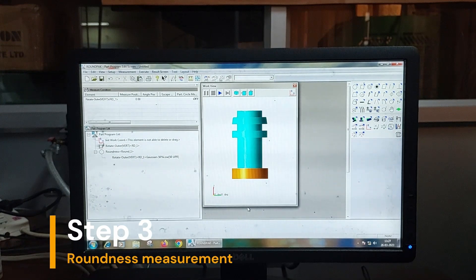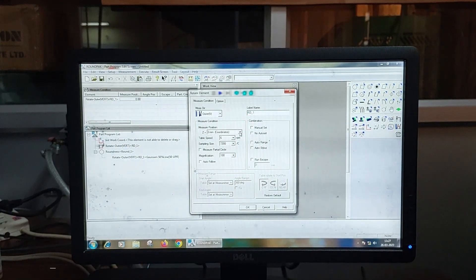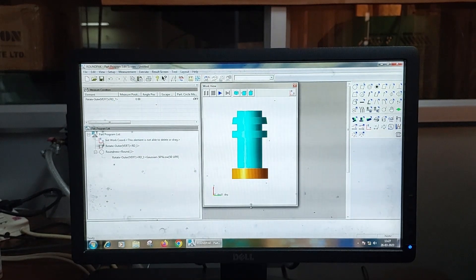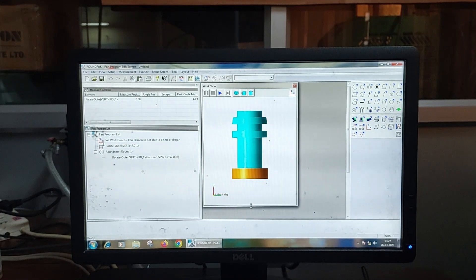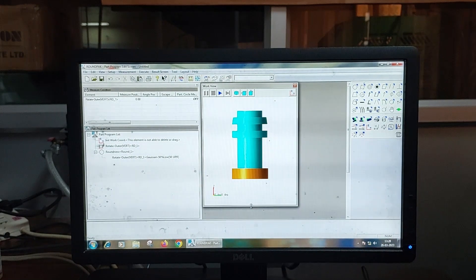The third step is Measuring the roundness. We have to enter the coordinates where we want to measure the roundness. Once the instrument is set up, the measurement process can begin. The operator initiates the measurement and the instrument starts rotating the specimen while the measurement probe traces its surface. The instrument software collects data on variations in diameter and roundness of the specimen.